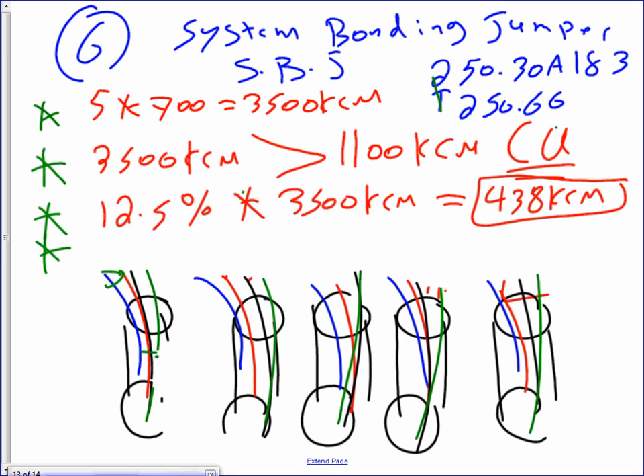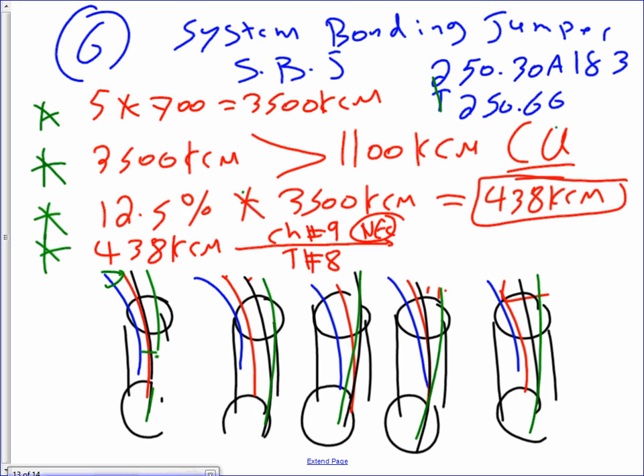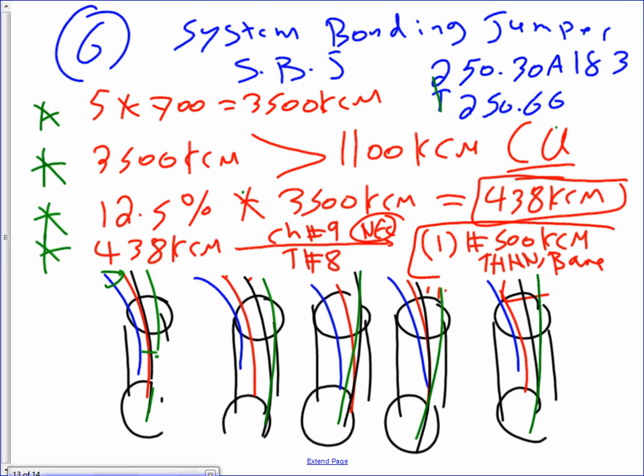So in a case like this, what do you do? You take the 438 kcm, take this one to NEC chapter 9, table 8, gentlemen, and that will get you one conductor, number 500 kcm THHN or bare. Okay.